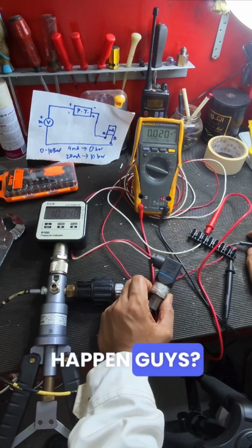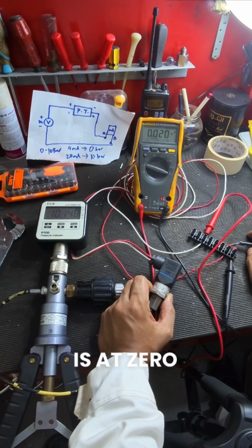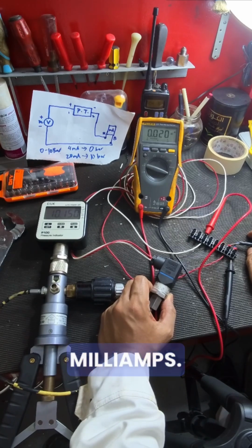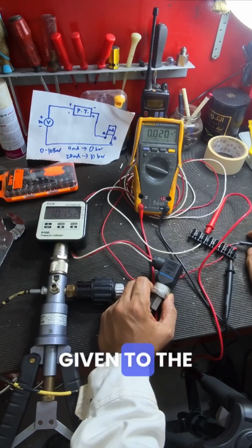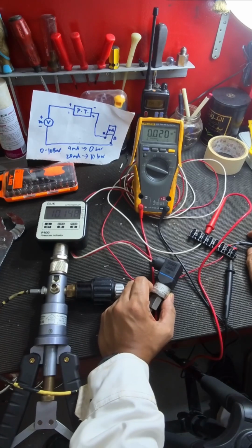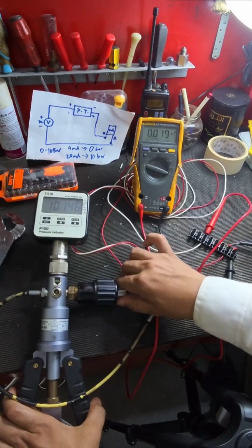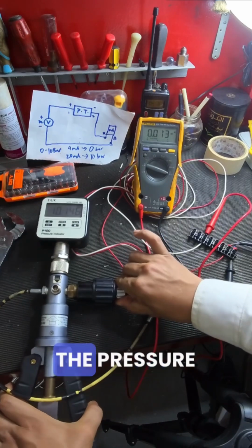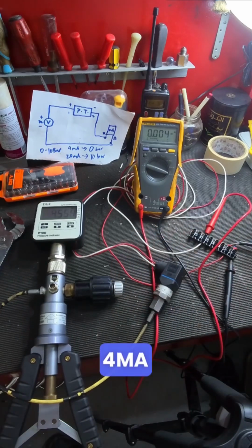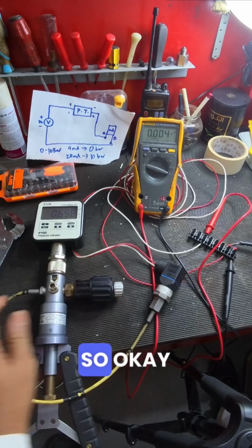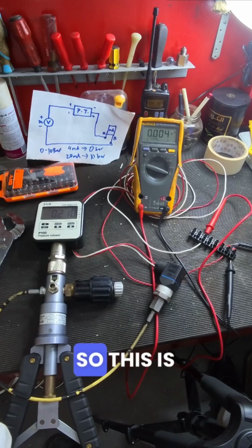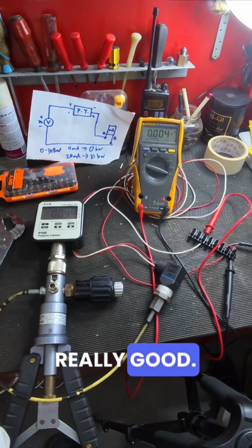So what will happen, guys, is that at 0 pressure it gives 3 milliamps. That's the time it gives alarms to the system, in our system. Okay, that's it. So let's release the pressure and go back to 4 milliamps. So okay, guys, this is really good now.